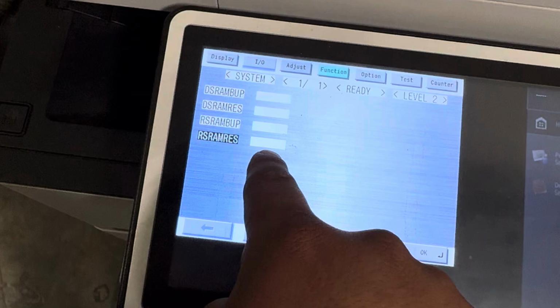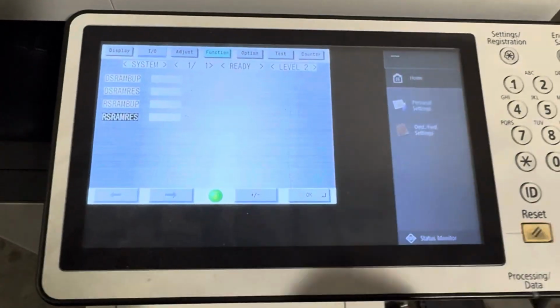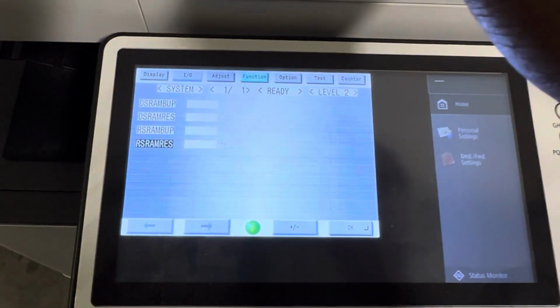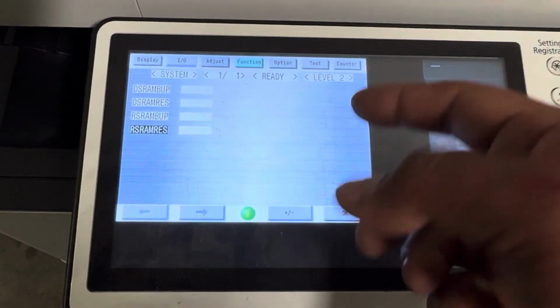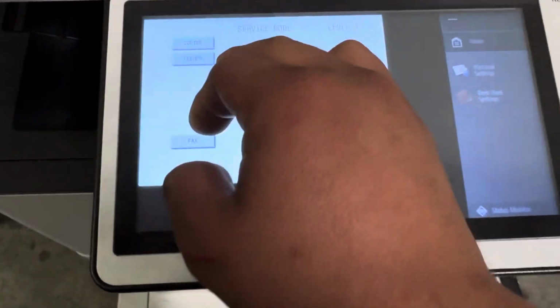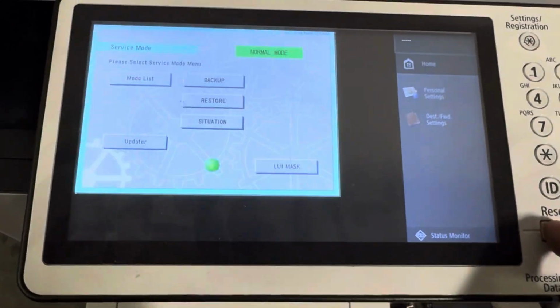You're going to hit that, make sure it's highlighted, press OK, and once this little square here says OK, you're all good to go. All the information that we backed up before we cleared it is back in that PCB board, which is the reader controller. If you continue getting that code after you reset it, then there's something wrong with the information that it had before. So come back, go to level 1, go to clear, do the RAM clear again, and then turn it back on. If the error code is gone, then you've solved the issue.